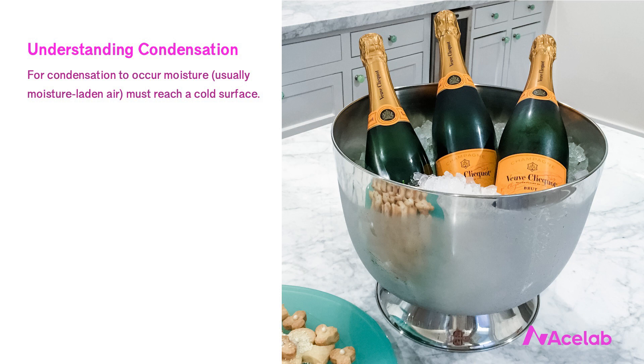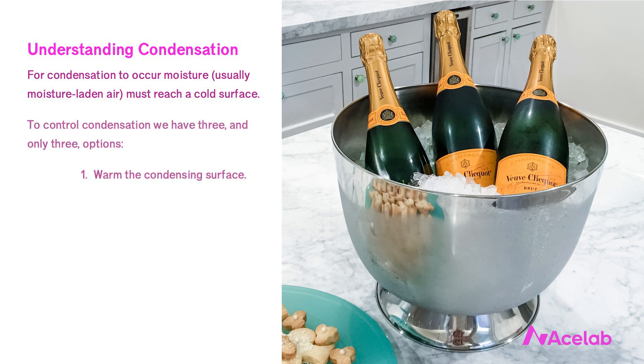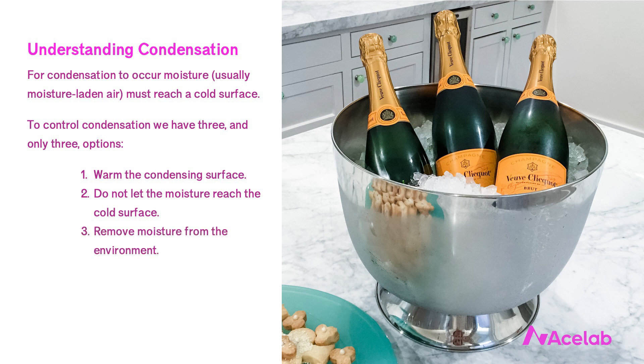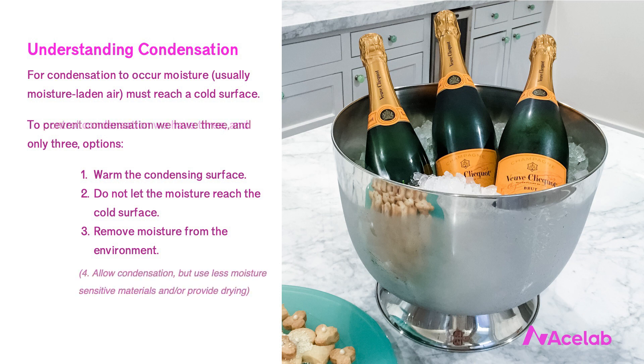For condensation to occur, moisture-laden air must reach a cold surface. To prevent condensation, we have three options: we can warm the condensing surface (no cold surface, no condensation); we can prevent moisture from reaching the cold surface; or we can remove moisture from the environment, usually by dehumidifying. In building design, we don't actually need to prevent condensation — we need to control it. A little condensation is okay as long as it doesn't cause building materials to decay. This introduces a fourth option: allow condensation to occur, but either use materials that aren't at risk of damage or provide enough drying to prevent damage. We usually pursue these four strategies in combination.